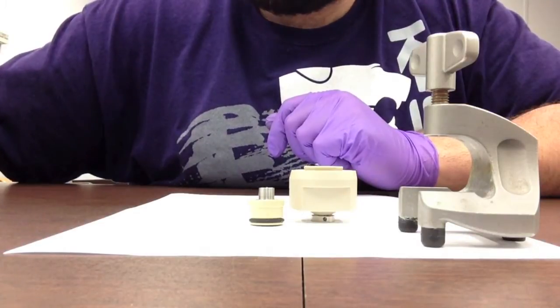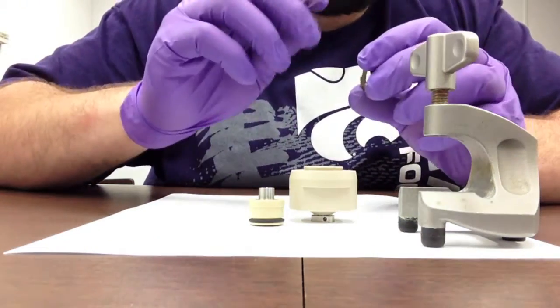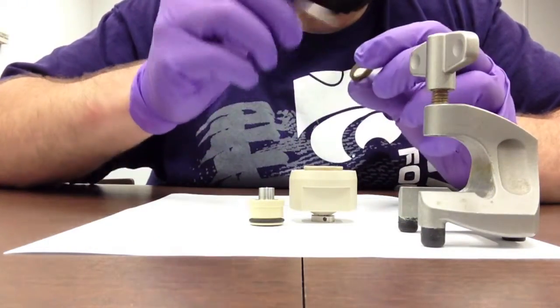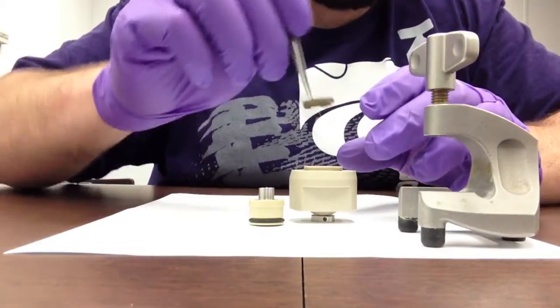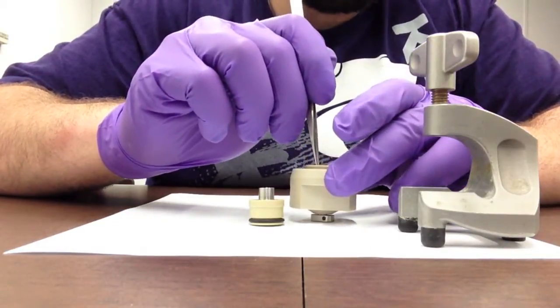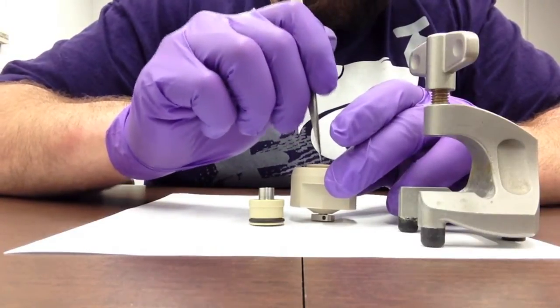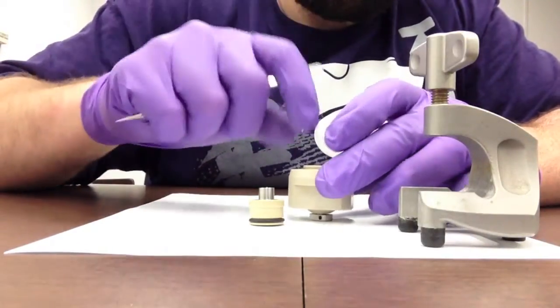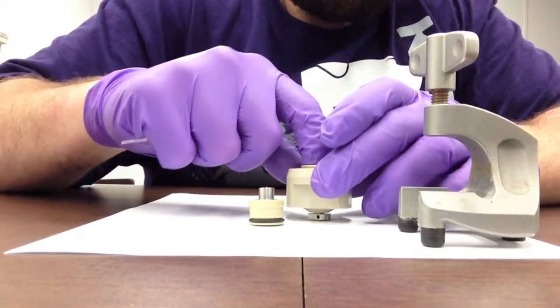On top of that, we have a specially designed spacer ring that has some cleats on it. These cleats are designed to protect our electrode from being crushed. We have a nanowire design in which we do not want to crush those wires, so this acts like a special cleat to protect those and will not allow anything to touch the main parts of the electrode.